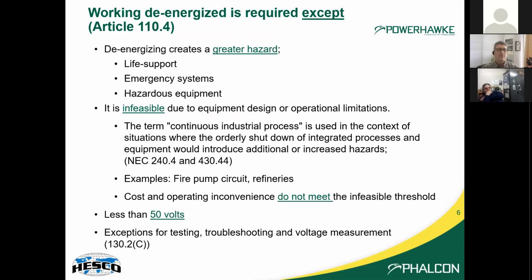There are a few exceptions you'll see in Article 110.4 to this idea of working de-energized: when it creates a greater hazard, when it's infeasible, and when it's less than 50 volts.